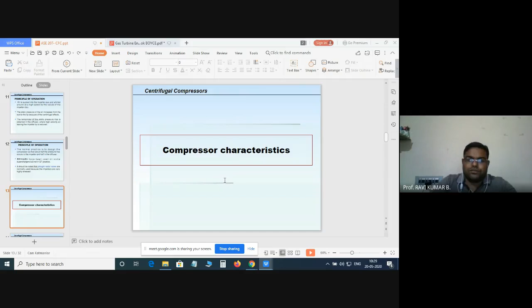The performance of a compressor can be evaluated with the help of certain charts or curves. Those are known as compressor characteristic curves. The performance of a compressor may be specified by curves of delivery pressure and temperature against mass flow rate. We draw the parameters with the y-axis as delivery pressure or temperature, and the x-axis as mass flow rate, and we get certain variation. Those variation curves are known as characteristic curves. These characteristic curves, however, are dependent on other variables such as conditions of pressure and temperature at entry of the compressor and the physical properties of the working medium.